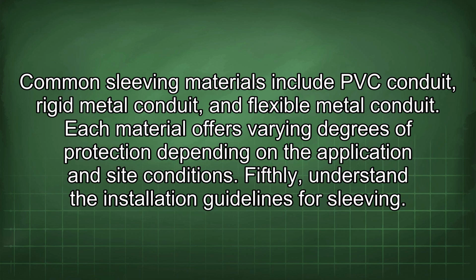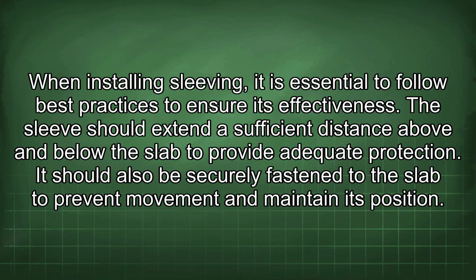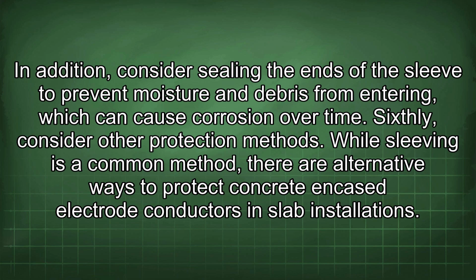Fifthly, understand the installation guidelines for sleeving. When installing sleeving, it is essential to follow best practices to ensure its effectiveness. The sleeve should extend a sufficient distance above and below the slab to provide adequate protection. It should also be securely fastened to the slab to prevent movement and maintain its position. In addition, consider sealing the ends of the sleeve to prevent moisture and debris from entering, which can cause corrosion over time.